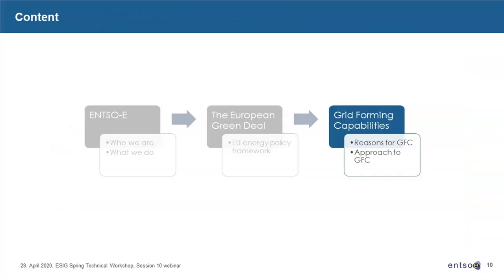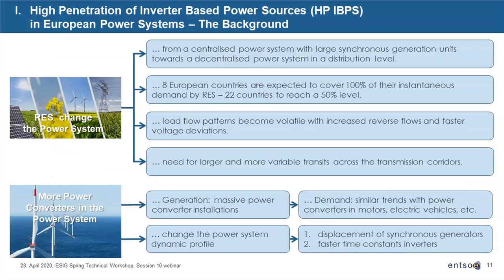All of this contributes to and even accelerates the transition of the electricity system, transmission system, and supply system, and leads to an even more accelerated displacement of traditional conventional synchronous generation by RES sources, which are mainly inverter-based power sources. A number of characteristics of how RES changes the power systems is listed here. We move from a centralized system to a distributed power system. A lot of generation will be at distribution levels.